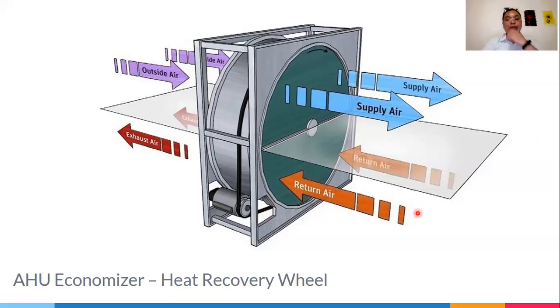So one downside of this, for example, whatever particle or contaminant this return air has will likely be passed to the outside air, because this return air will touch the medium, or the silicone wheel that rotates here, and then that silicone will have contact with the outside air. So whatever contaminant or particle is in the return air will also be transferred to the outside air or supply air. Sometimes you don't want these particles or contaminants to mix or mingle together.